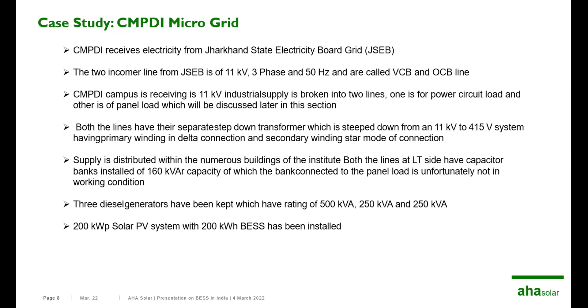This was a scenario with two incomers, but power outages were very common there. The authority wanted to install a system for uninterrupted power supply. There were also 3 DG sets with a cumulative capacity of 1 MVA, but we know diesel consumption cost is very high nowadays. So we installed a 200 kilowatt system. The building terrace wasn't that big, but it was enough to install a 200 kilowatt solar PV system, along with a BESS capacity of 200 kWh.